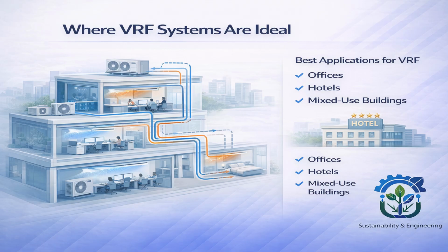Now let's talk about hotels. Hotels are one of the best applications for VRF. Why, you may ask? Because every room is an independent zone, occupancy keeps changing for each room, and guests expect individual temperature control. So with VRF, one room can be fully loaded, another room can be switched off, and another room can operate at partial load. The system automatically adjusts refrigerant flow, saving energy while maintaining comfort. This is something conventional DX systems struggle to manage efficiently.